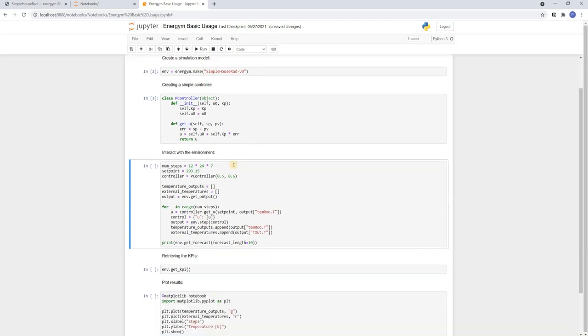To run the model in closed loop we need to specify a few more options. The first is the number of steps we want to make. Since the model has an internal time step of 5 minutes, so 12 steps per hour, we use 12 times 24 times 7 to simulate one week. As a set point we choose 293.15. The temperature units for this model are in Kelvin, so this corresponds to 20 degrees Celsius.